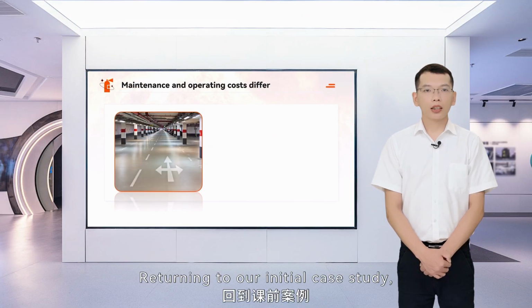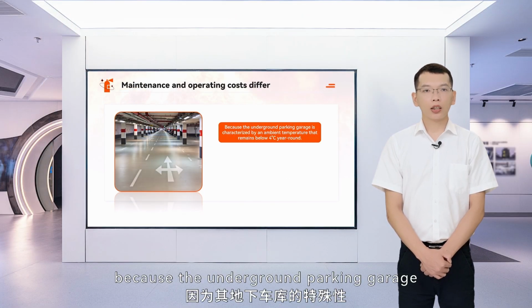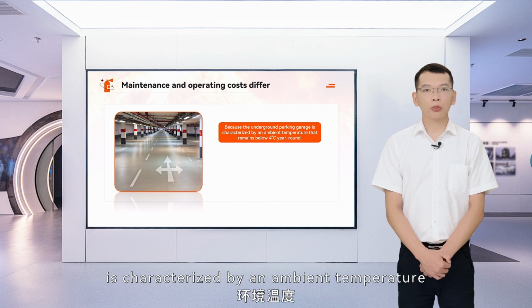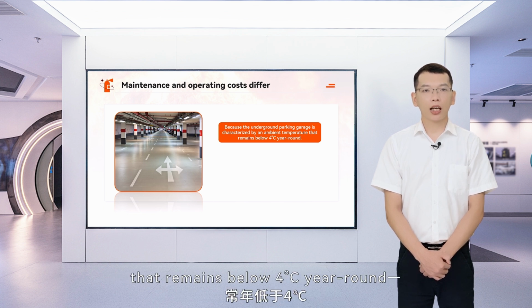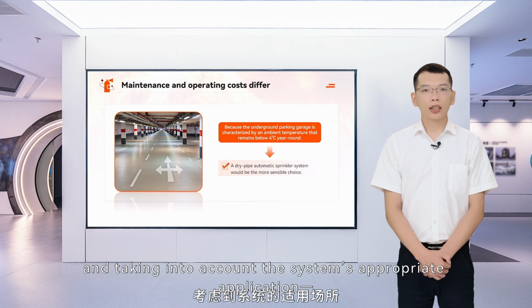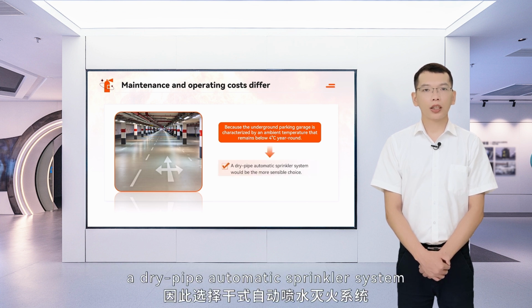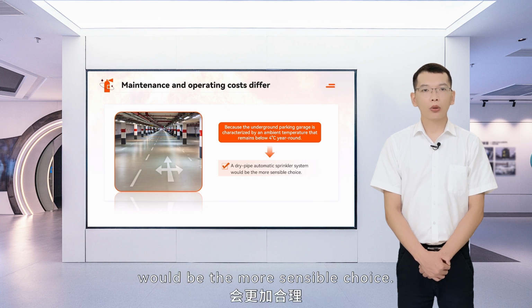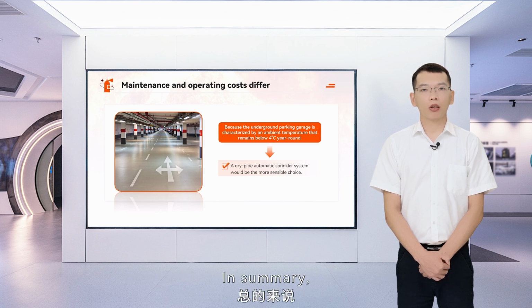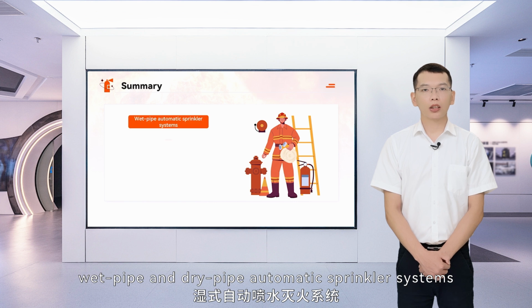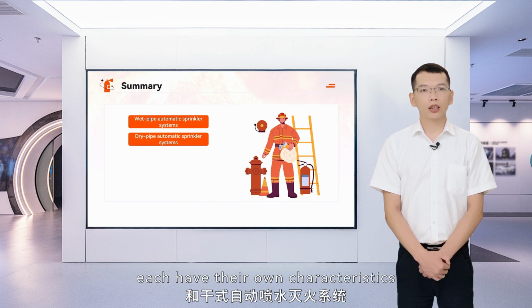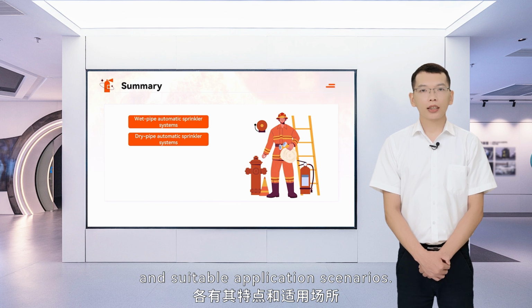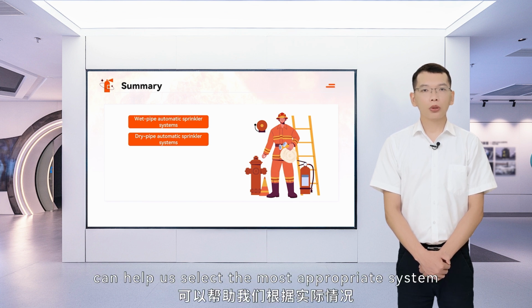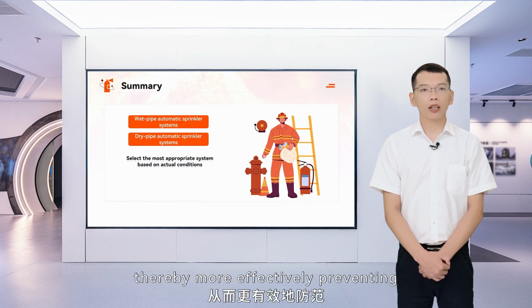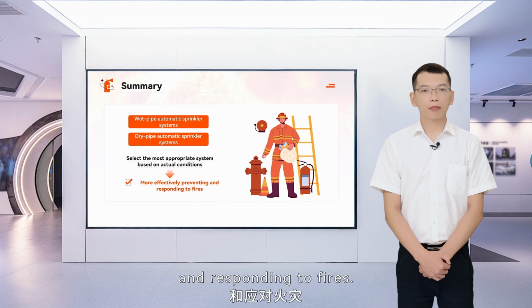Returning to our initial case study, because the underground parking garage is characterized by an ambient temperature that remains below 4 degrees Celsius year-round, and taking into account the system's appropriate application, a dry pipe automatic sprinkler system would be the more sensible choice. In summary, wet pipe and dry pipe automatic sprinkler systems each have their own characteristics and suitable application scenarios. Understanding these differences can help us select the most appropriate system based on actual conditions, thereby more effectively preventing and responding to fires.